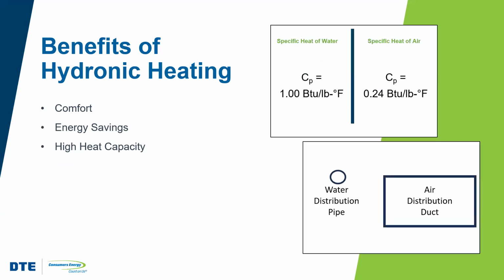And that's largely because water has a higher specific heat than air. So as a heat transfer fluid, a pound of water has a heat carrying capacity that is more than 4 times that of a pound of air. But of course, when we're talking about heat transfer, we don't talk in terms of weight, right? We don't talk in terms of pounds of fluid. We talk in terms of volume. You got cubic feet for air, gallons for water.